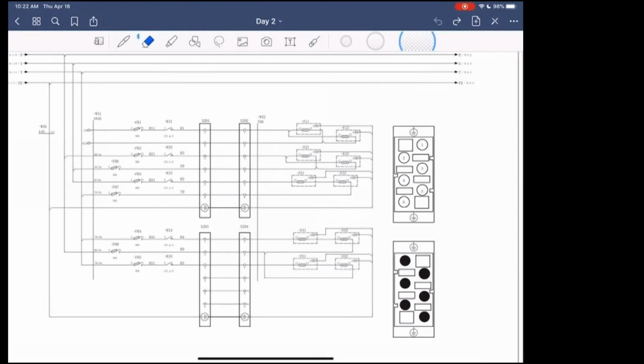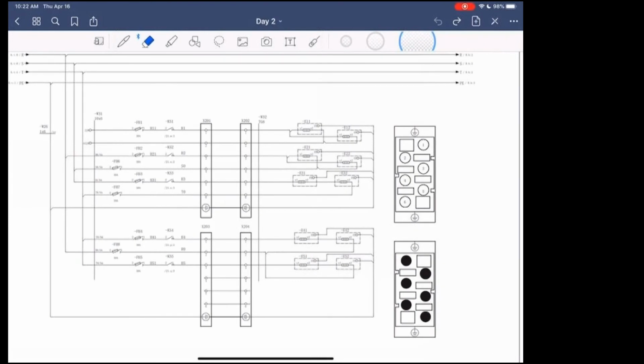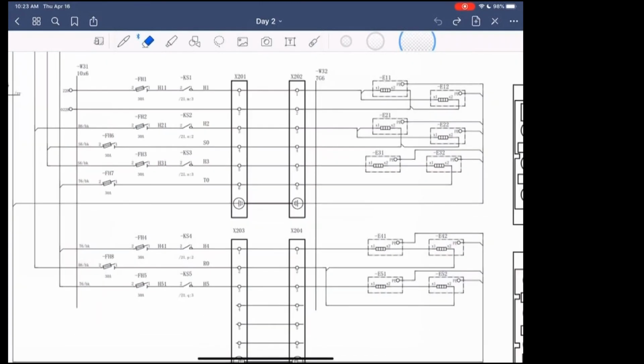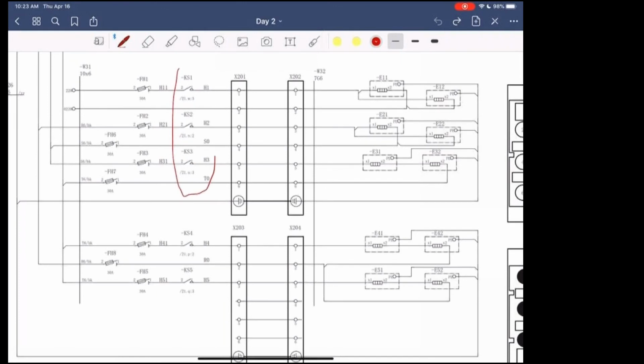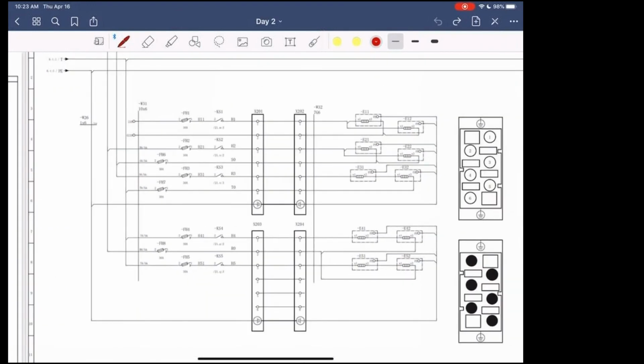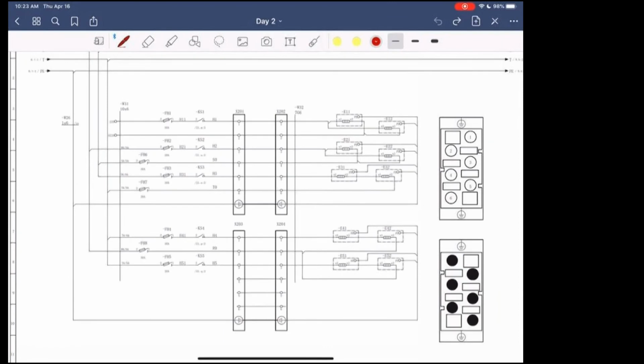And again, this is the heater band circuit. I'm showing you the actual wiring diagram and the plug connectors. And these are your SSRs, solid state relays, which open and close to turn the heats on and off. And you have your fuses, your 30 amp fuses for the circuits. Another thing to keep in mind, they use the 3 phases of the system for this. So they have phase 1, phase 2, I'm sorry, phase 2 and phase 3.